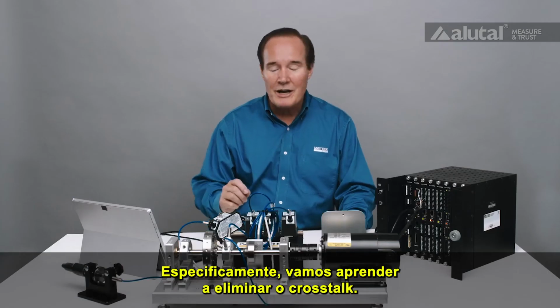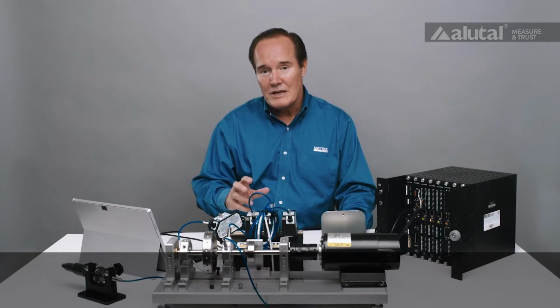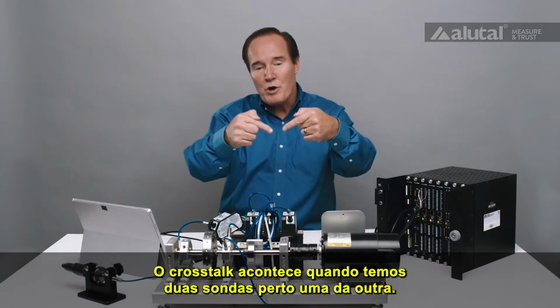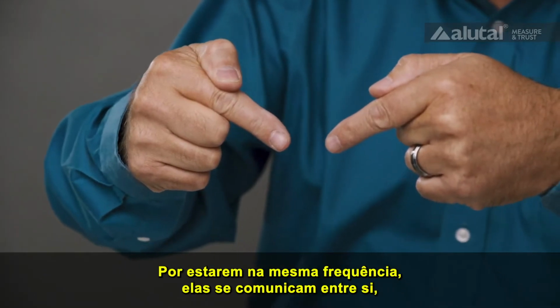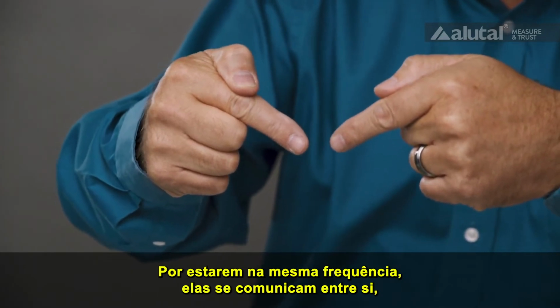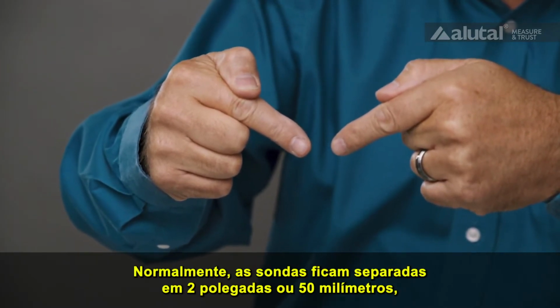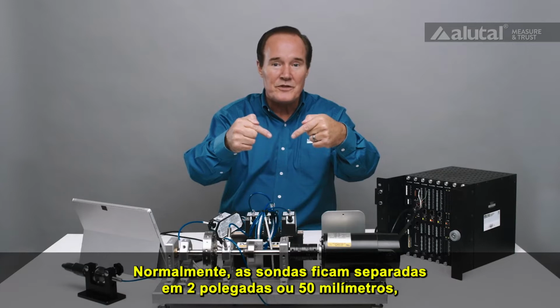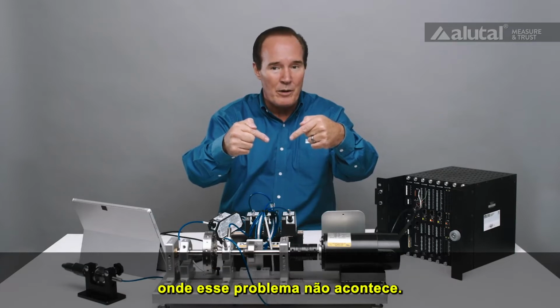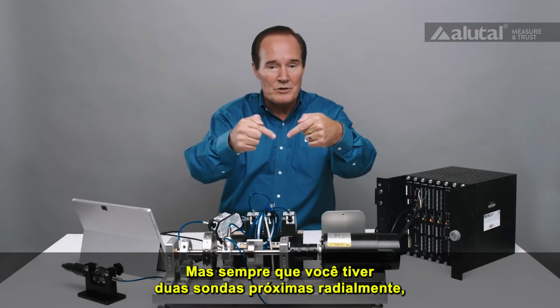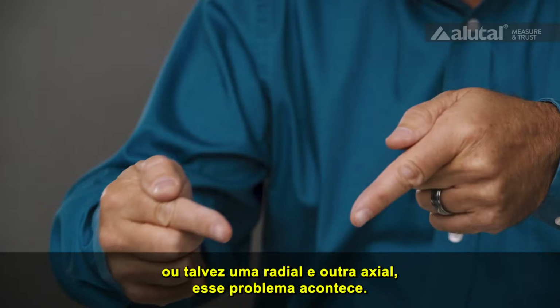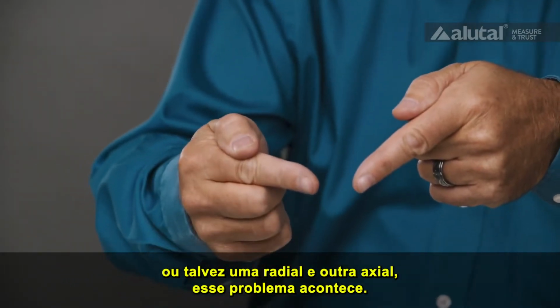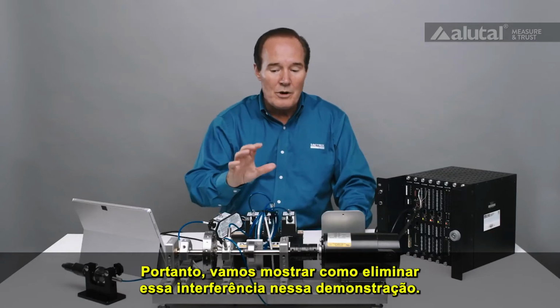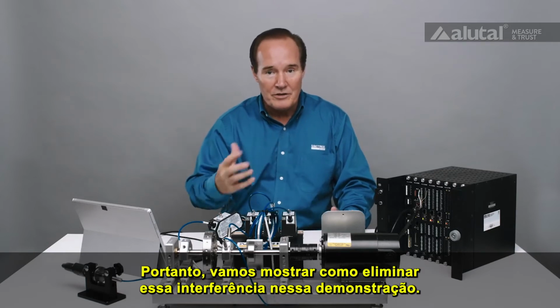Specifically, we're going to talk about how we eliminate crosstalk. Crosstalk occurs when you have two probes that are close together. And because they're at the same frequency, they talk to each other, and it causes a problem. Typically, probes are 2 inches or 50 millimeters apart where you don't have that problem. But anytime you have two probes close together radially, or maybe one radial, one axial, you can have this problem. So what we're going to show is how we get rid of it during this demonstration.